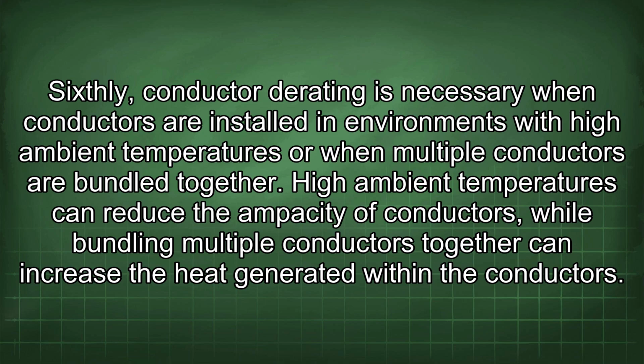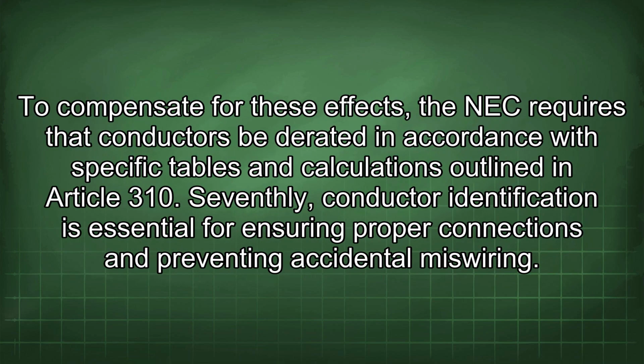Sixthly, conductor derating is necessary when conductors are installed in environments with high ambient temperatures or when multiple conductors are bundled together. High ambient temperatures can reduce the ampacity of conductors, while bundling multiple conductors together can increase the heat generated within the conductors. To compensate for these effects, the NEC requires that conductors be derated in accordance with specific tables and calculations outlined in Article 310.